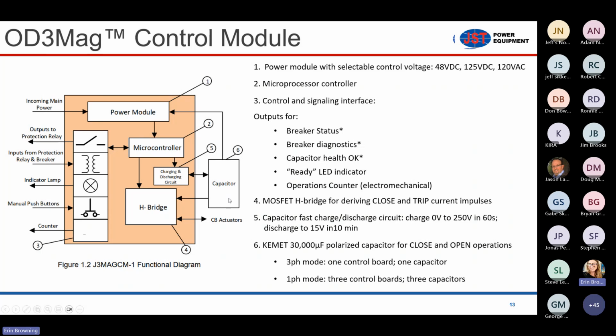So the capacitor, again, it discharges through the control board to the actuator, and then there's a control interface for inputs and outputs, and this is what gets wired to terminal blocks for customer use. And that would be things like, there's a position indicator, there's an operations counter, there's status outputs like capacitor health, but also overall breaker health. So this is how the customer has some visibility into the status of the breaker.